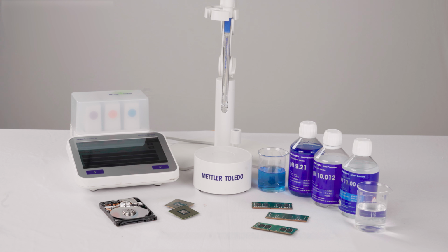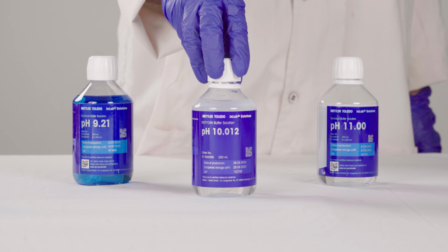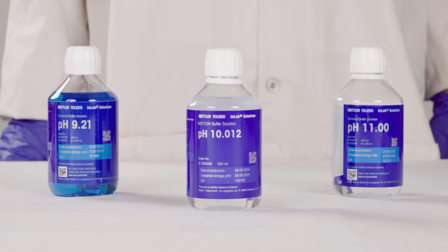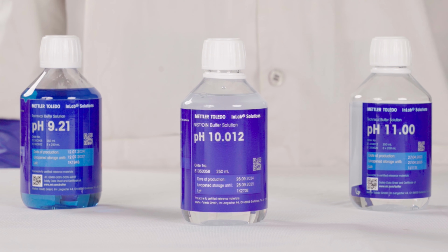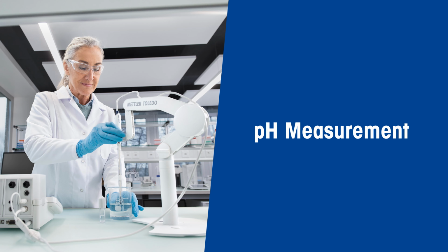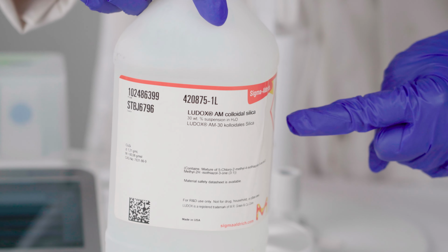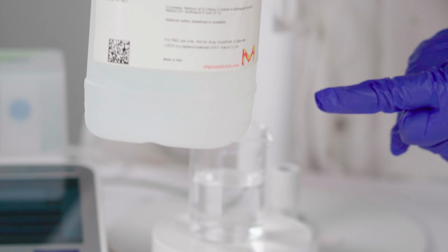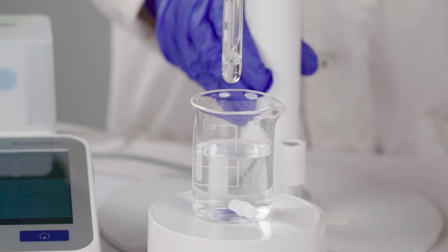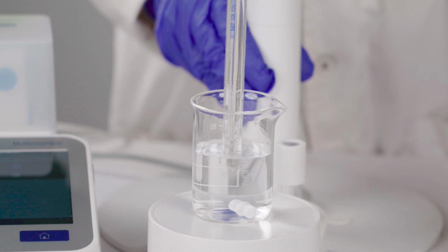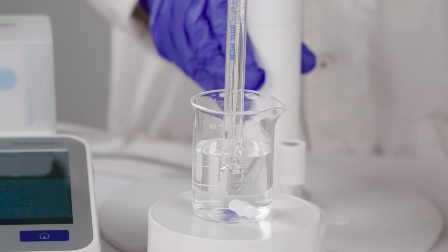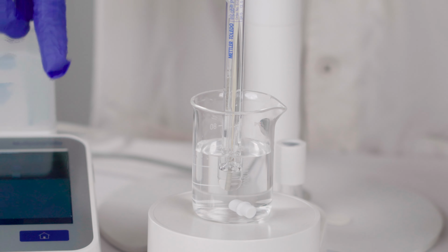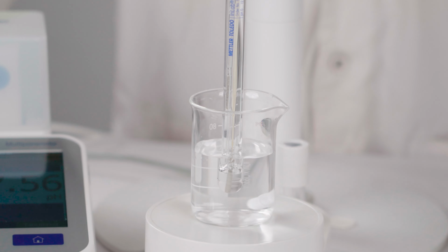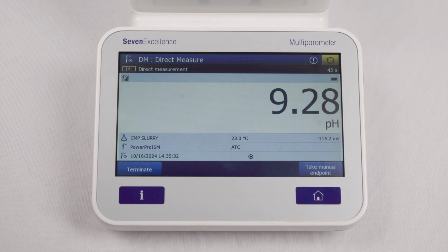Once you've calibrated the sensor, it's time to verify with a known pH buffer that falls within the calibration range, but differs from the buffers used for calibration. Now let's move on to measuring the pH of your sample. All you need to do is pour around 30 milliliters of CMP slurry into a beaker and dip the pH sensor in the mixture, ensuring that the sensor junction is entirely immersed in the sample. Then give it a gentle stir to ensure proper mixing, and record the pH.